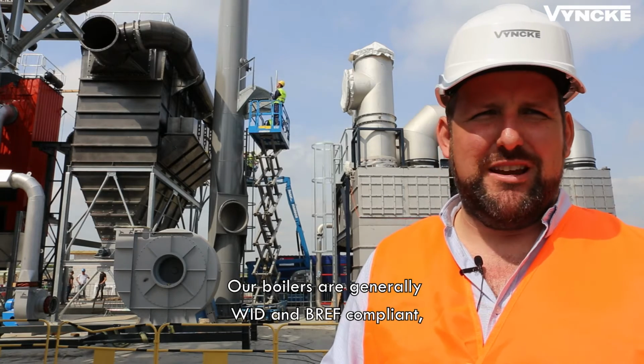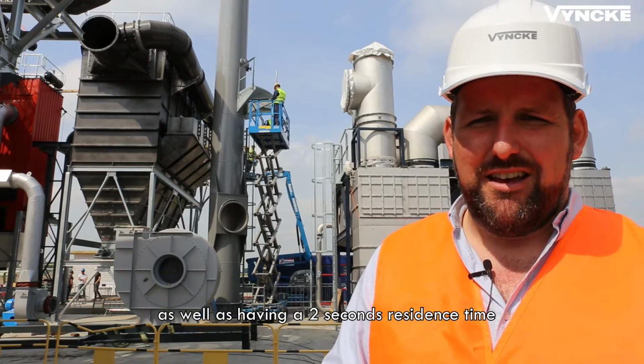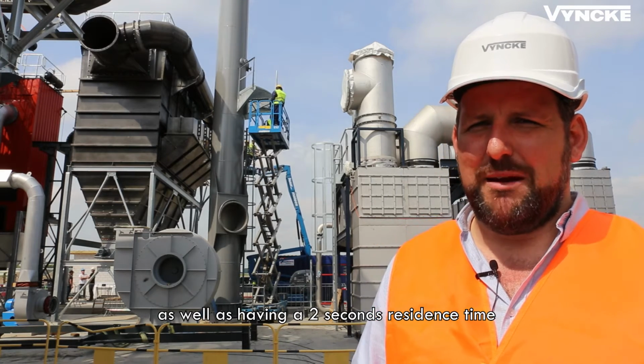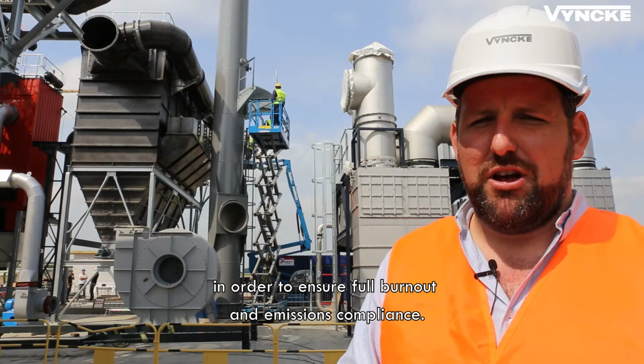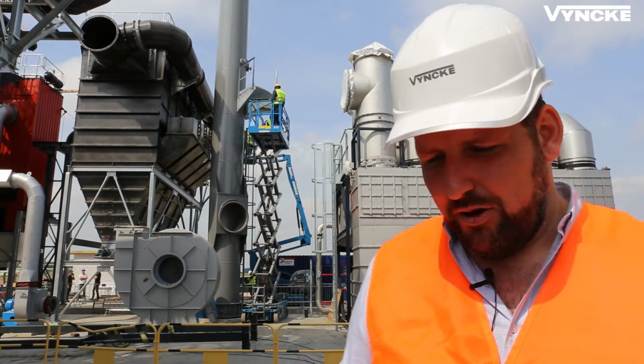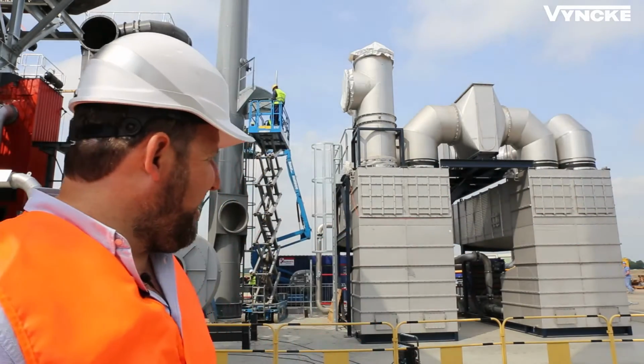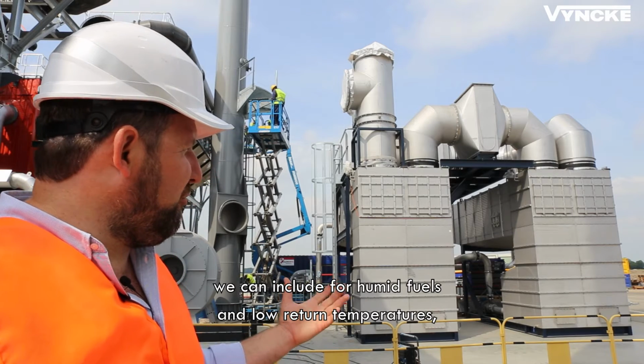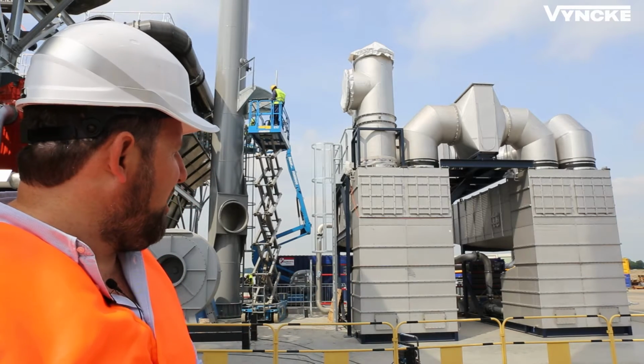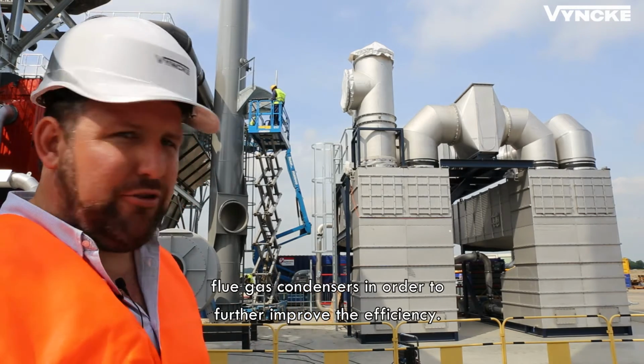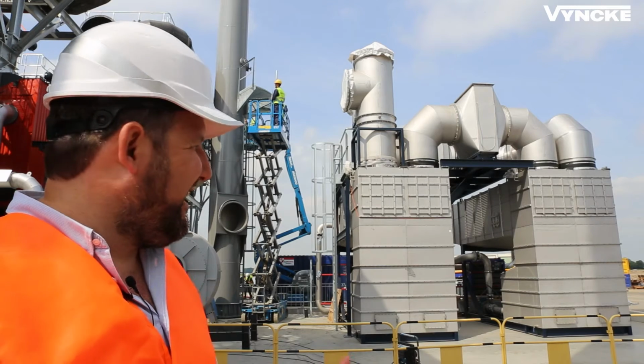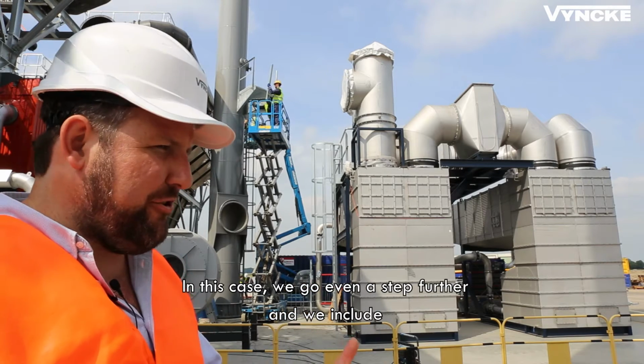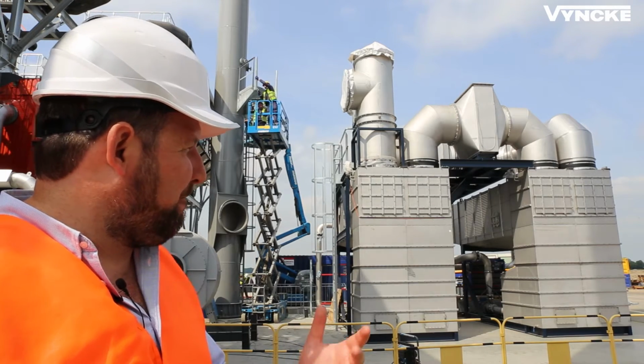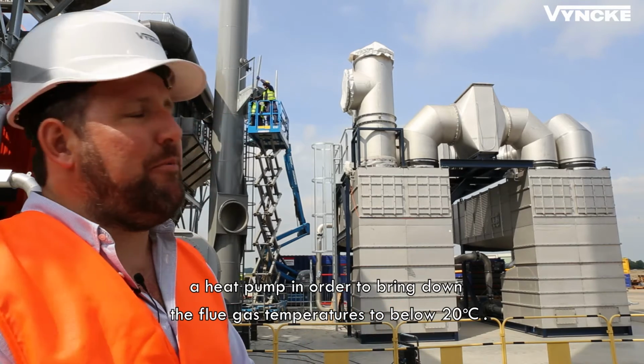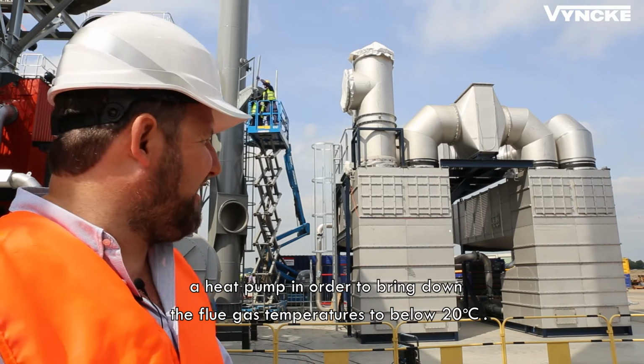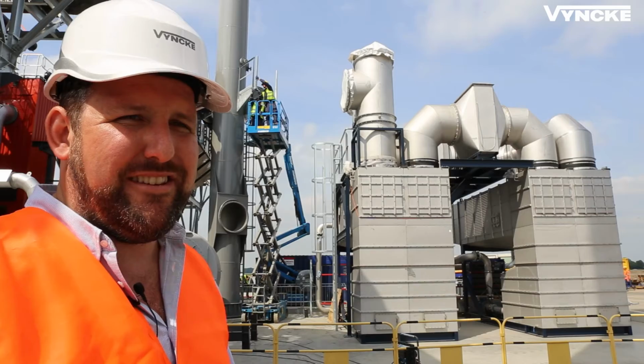Our boilers are generally WID and BREF compliant, as well as having a 2 seconds residence time in order to ensure full burnout and emissions compliance. With regards to efficiency, we can include for humid fuels and low return temperatures flue gas condensers in order to further improve the efficiency. In this case, we go even a step further and we include a heat pump in order to bring down the flue gas temperatures to below 20 degrees.